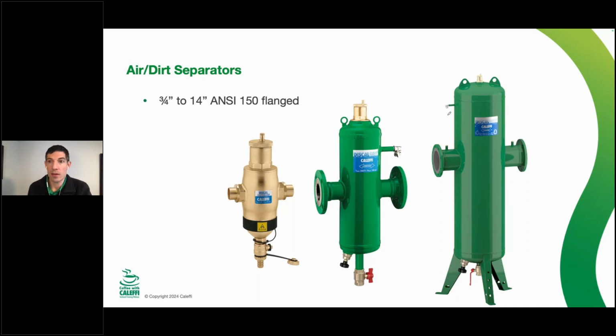And we did a glycol webinar earlier this summer. Glycol is great at not freezing. Other than that, it's something that we wrestle with in hydronic systems for air separation and heat transfer and things like that. So we had a really good webinar that's on the YouTube channel about glycol to go through some of the things that glycol is great for, but don't overdo it. We don't need a higher percentage than is required because it's just going to make all that harder, and just expect more time. And another good question, would putting an auto air vent on the return line suck air into a system?